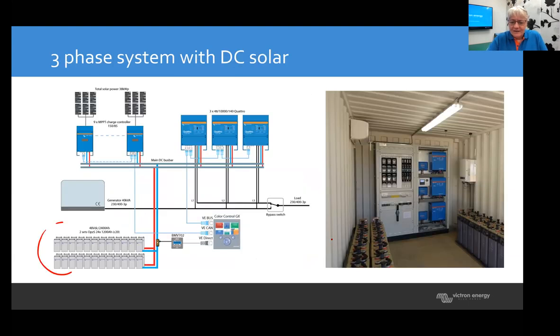Another thing they had here is a bypass switch, and that's an important thing to put in as well. What if something is wrong with one of the units in a 3-phase or parallel system? As soon as one unit stops, the whole bank turns off — the whole array of inverter chargers turns off. You still get DC solar, but no more AC. So you want to put a bypass switch in, so that if there's really something wrong with the system, you have a piece of paper or instructions with it: in case of trouble, press this switch or pull this lever, and we bypass the whole system.